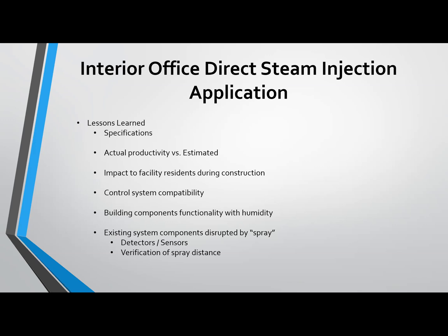Next, control system capability or compatibility. That is a huge learning right there. A lot of these newer systems are very technologically advanced -- sometimes they do too much. If the control system is older, it may not be able to communicate effectively or at all. We ran into a few situations where we had to make serious modifications. So I'd recommend doing a full investigation of whatever building automation control system exists, and make sure any equipment spec, especially voltage-wise and operationally and sequence-of-operation-wise, is compatible with what needs to operate, how it needs to operate, and how it needs to be monitored and alarmed.